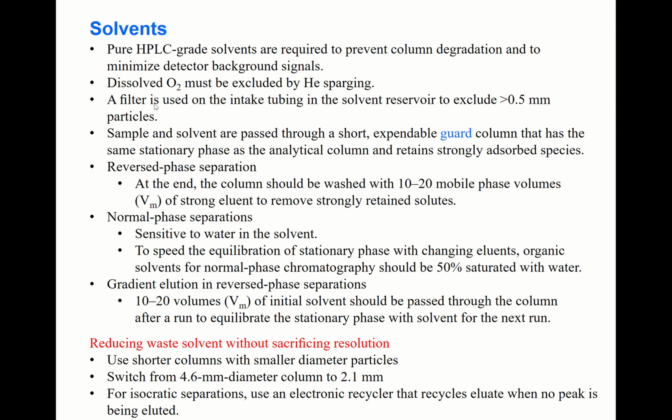A filter is used on the intake tubing in the solvent reservoir to exclude particles whose size is greater than 0.5 micrometers. Let me check. Wait just a second. Yeah, right, this is not millimeters, it is micrometers. I didn't convert this m to the Greek letter. So a filter is used to exclude the larger particles.